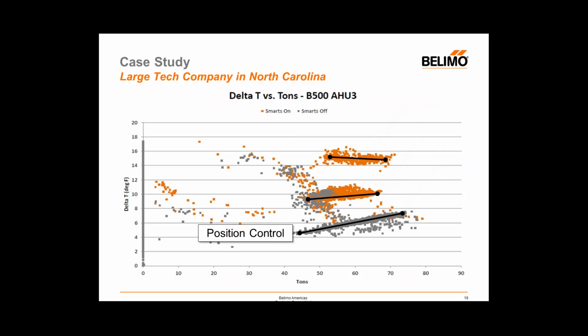So this bottom set of data here was when the valve was in what we call position control, which means that the control signal just controlled how open or closed the valve was. So this would be like a standard control valve in place. And you could see that the load range was anywhere from 45 to about 75 tons, and the cooling was done between 5 and maybe 7.5 degrees of delta T.